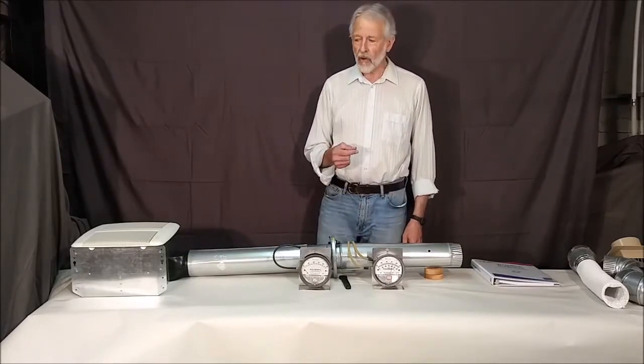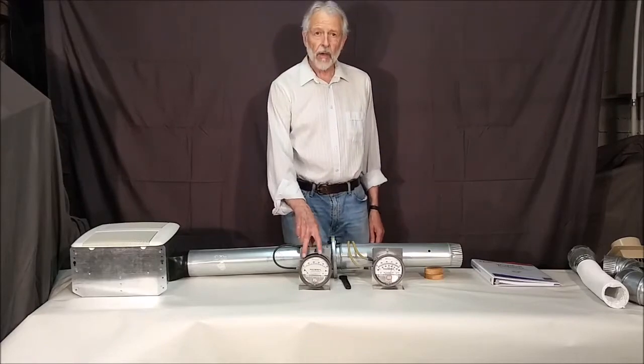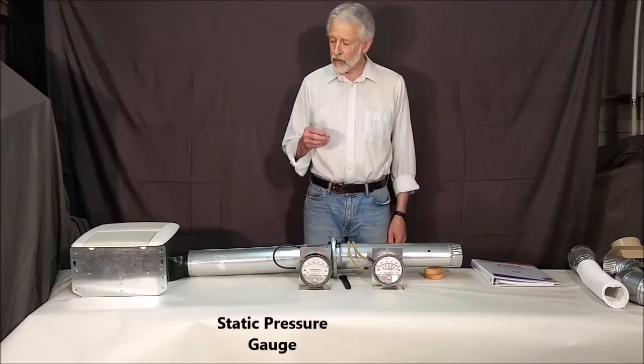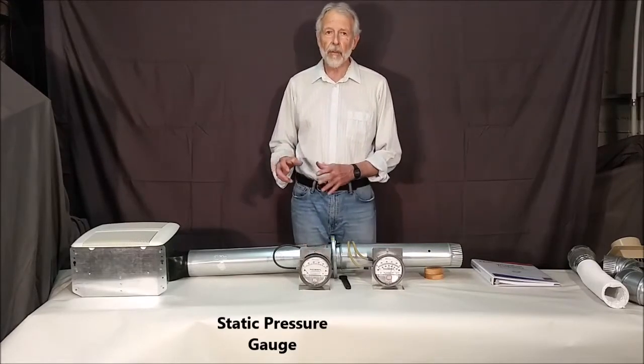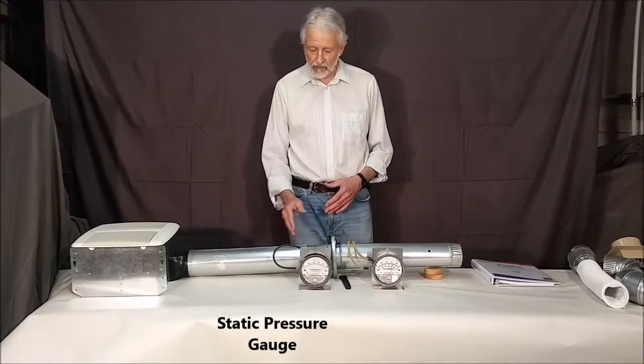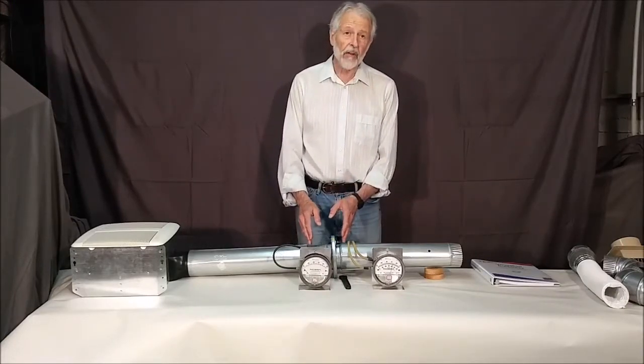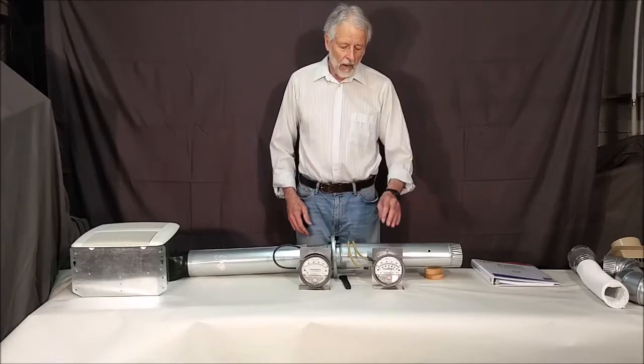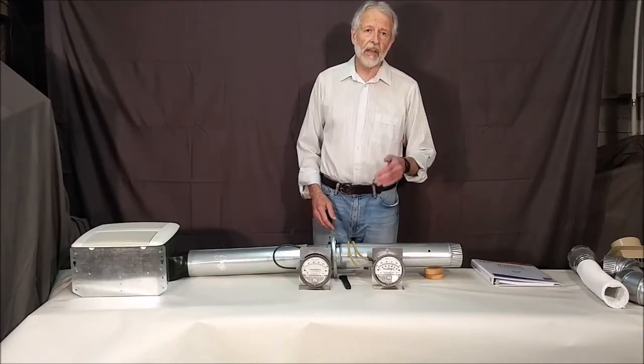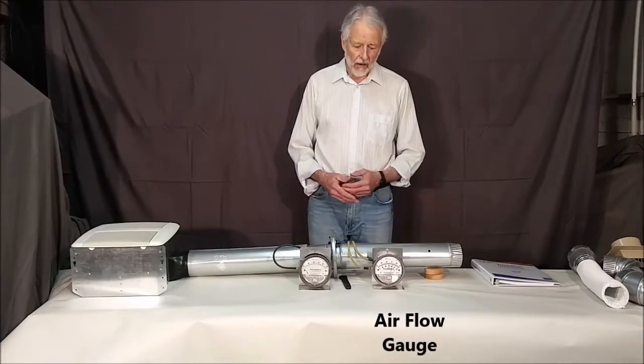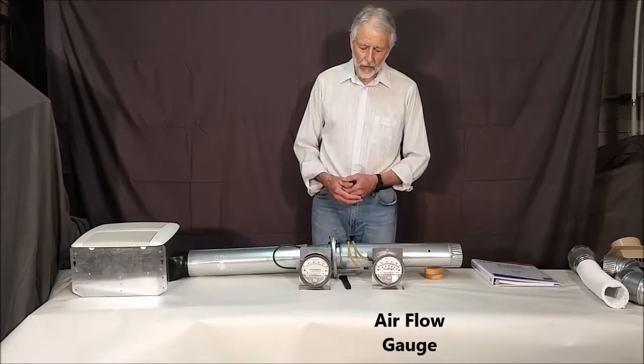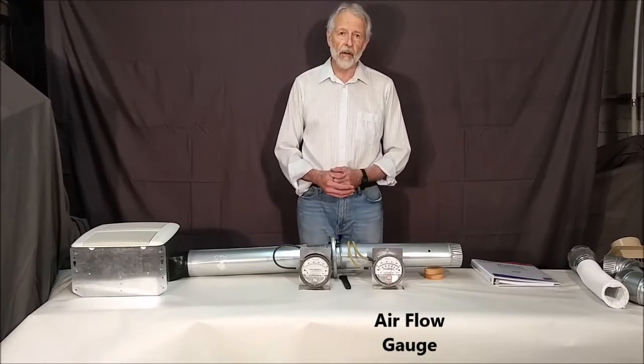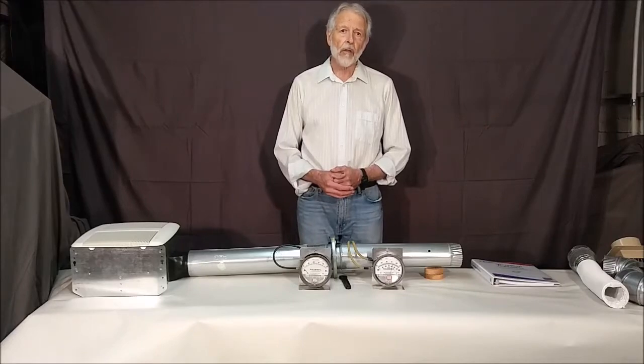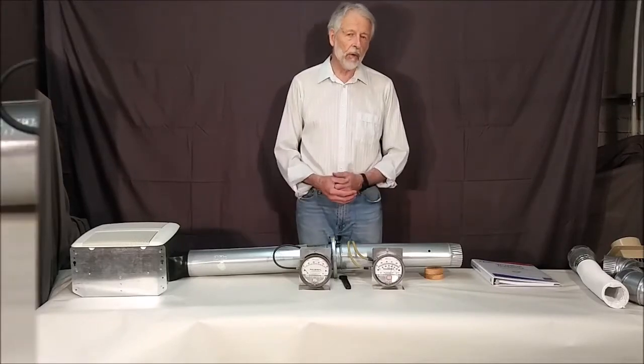The two instruments are, the one on your left is measuring the static pressure, which is the pressure the fan must develop in order to move air through the resistance of the duct and the turbulence of the measurement section. This gauge over here is indicating the flow rate of the fan. So the higher the needle goes here, the more airflow in cubic feet per minute is flowing through this system. Those are the two extreme conditions that we will use today.